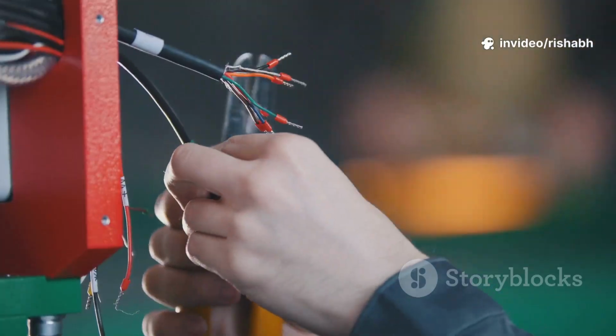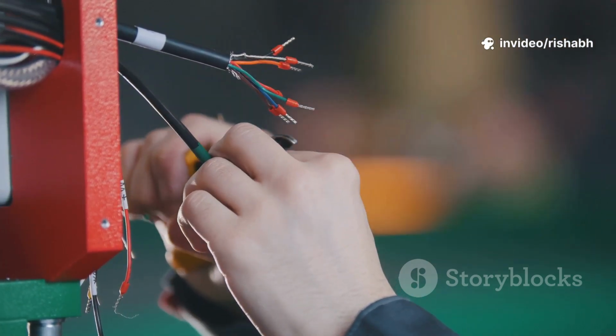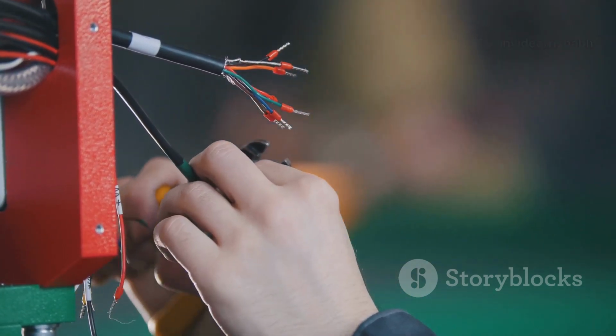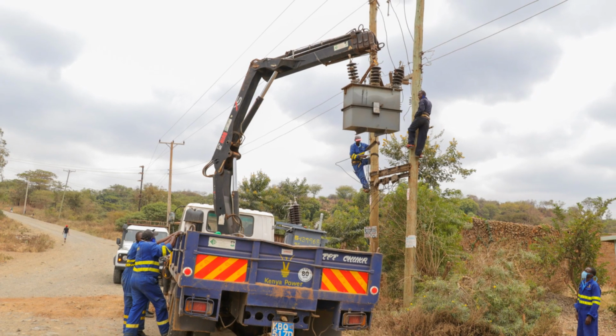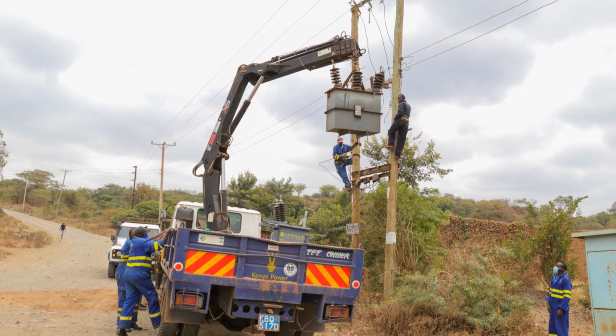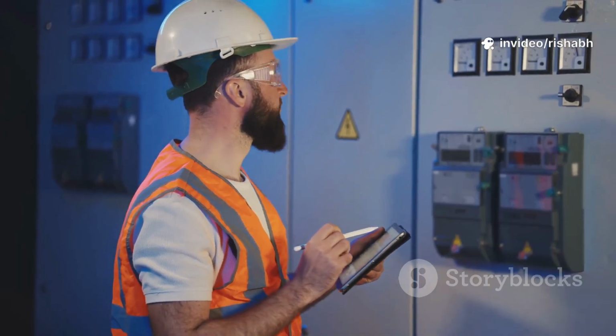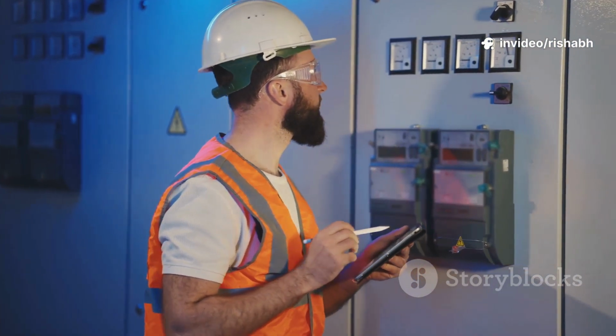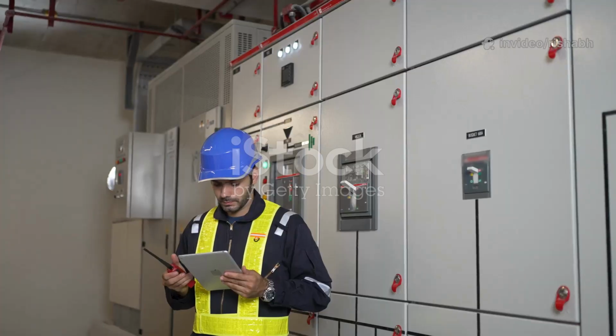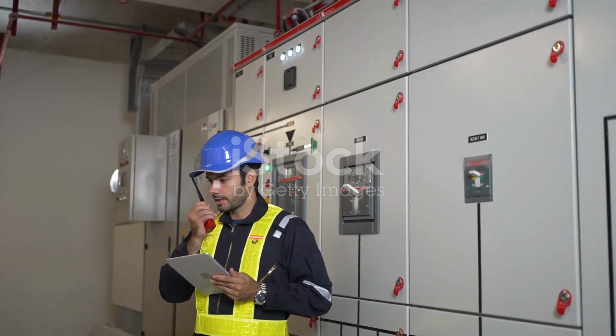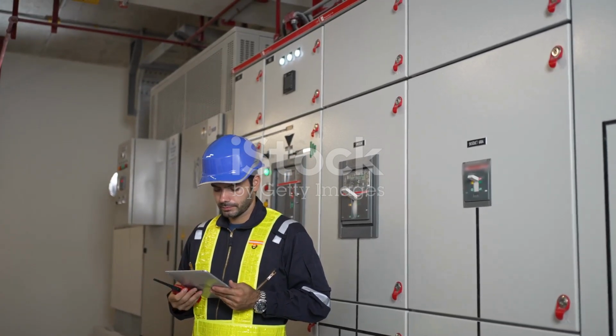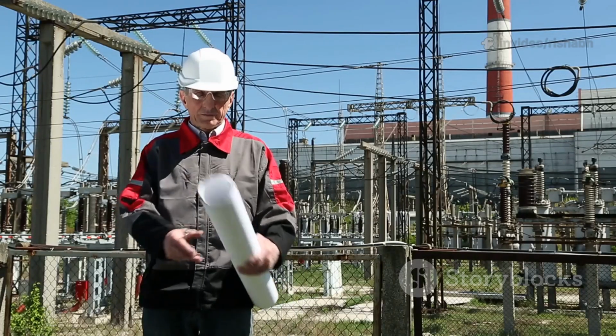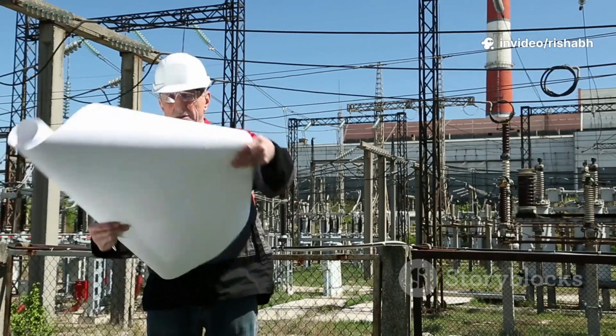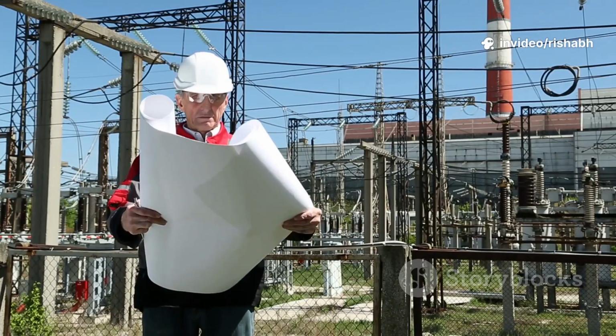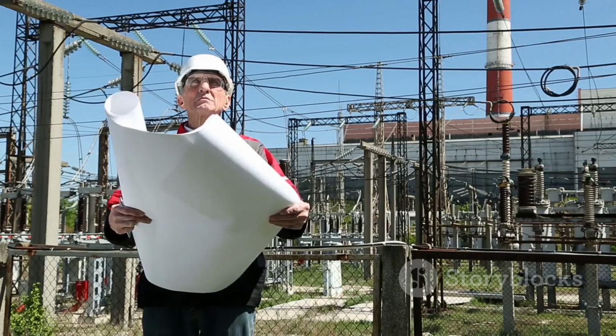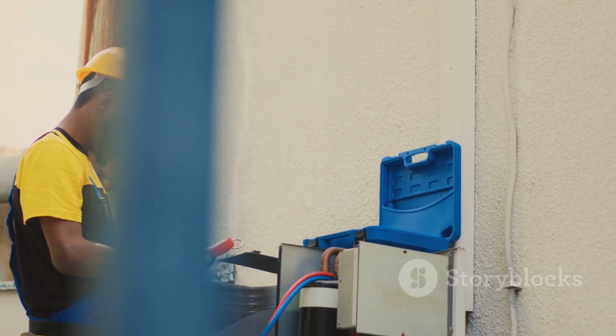develops. The device also keeps a close eye on the tap changer, a component that adjusts the transformer's output voltage. This part has many moving pieces and is one of the most common points of failure. The Multilin 845 monitors its operation, counting the number of times it has moved and tracking its performance. If it detects that the tap changer is getting stuck or taking too long to operate, it can flag this for maintenance. This proactive approach is a game changer. It means engineers can schedule repairs during planned downtime instead of having to react to a sudden, service-interrupting failure. It's preventative medicine for machines.